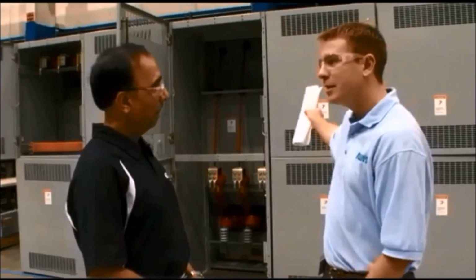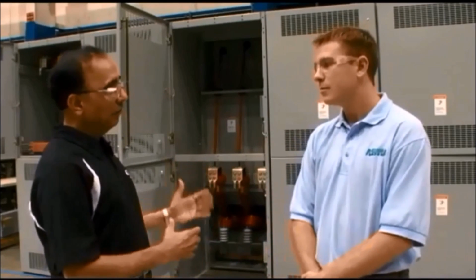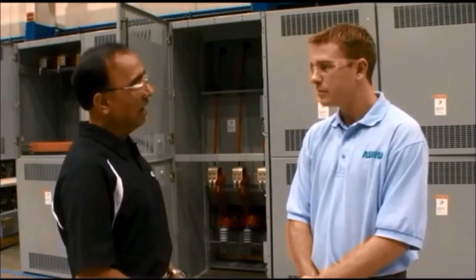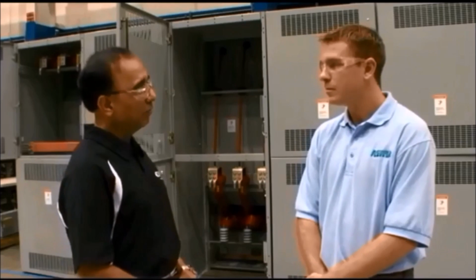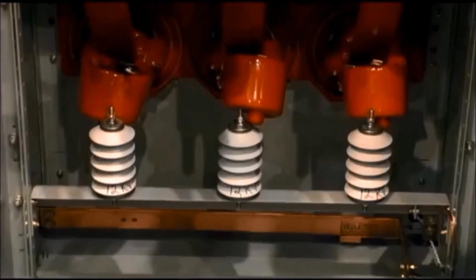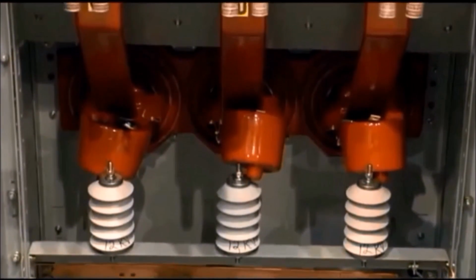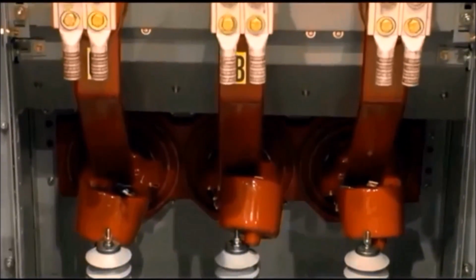How much power can this thing handle? This switchgear typically is applied at voltages from 2400 volts up to 38,000 volts, and it can carry currents from 1200 amps to 5000 amps.